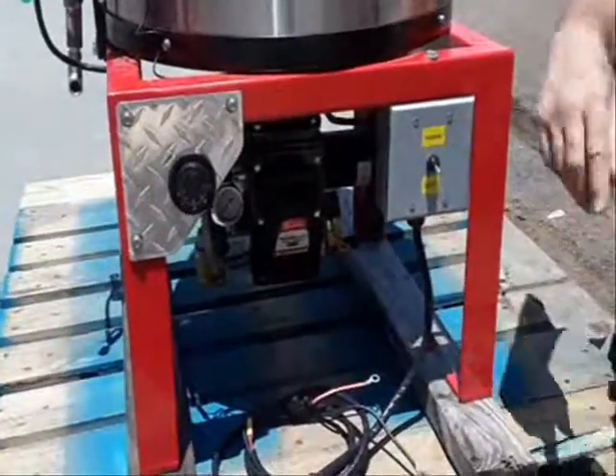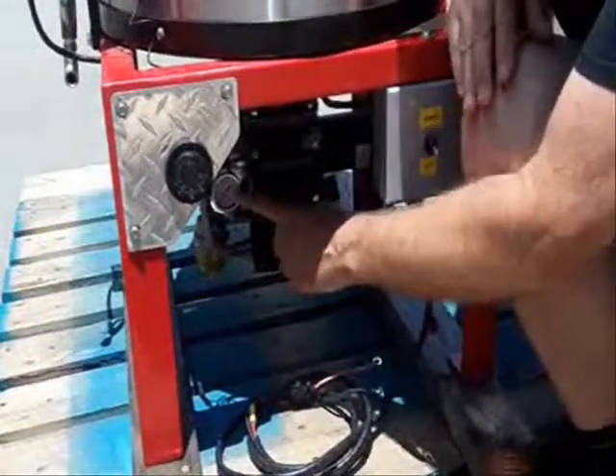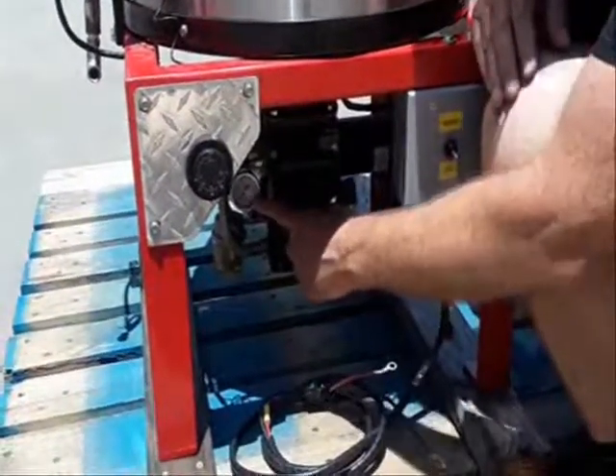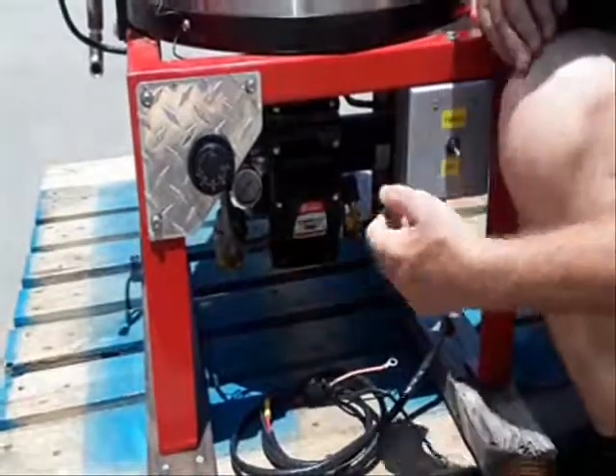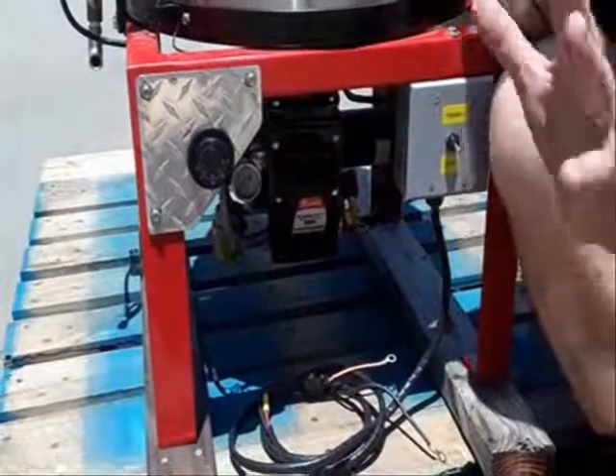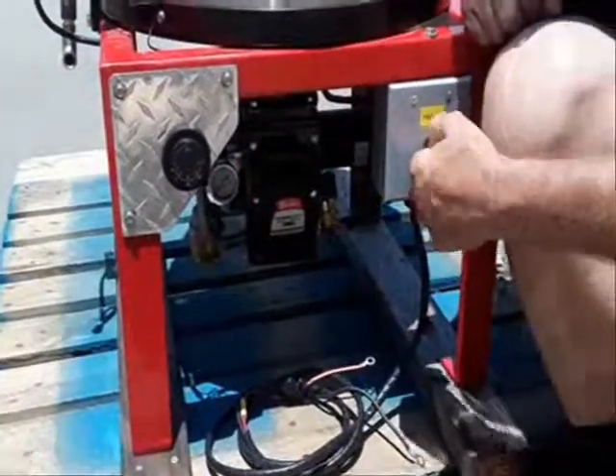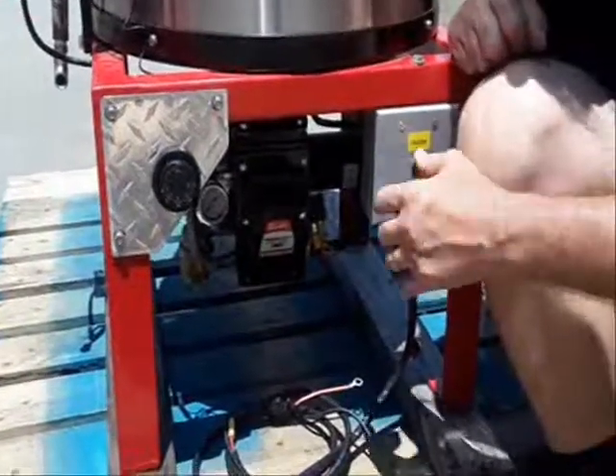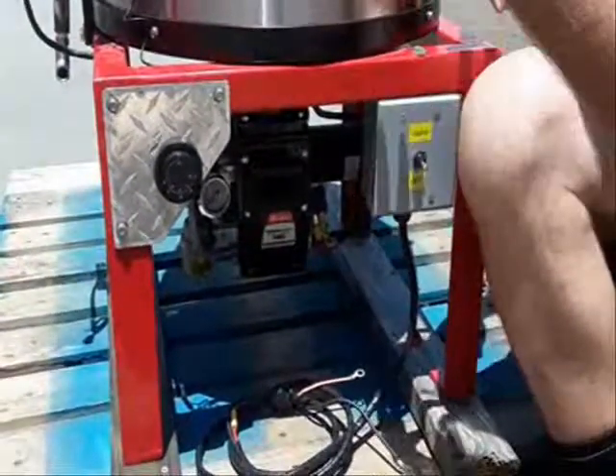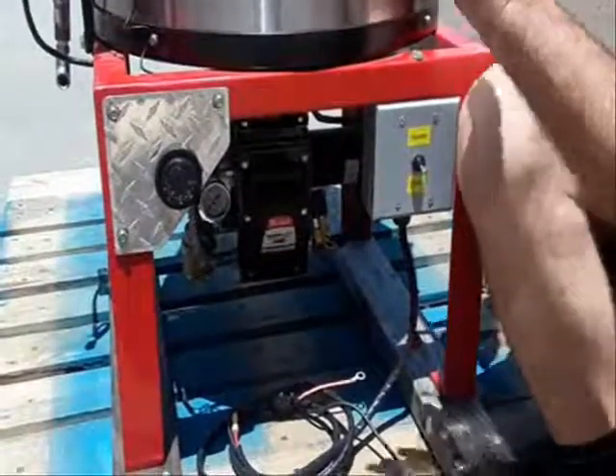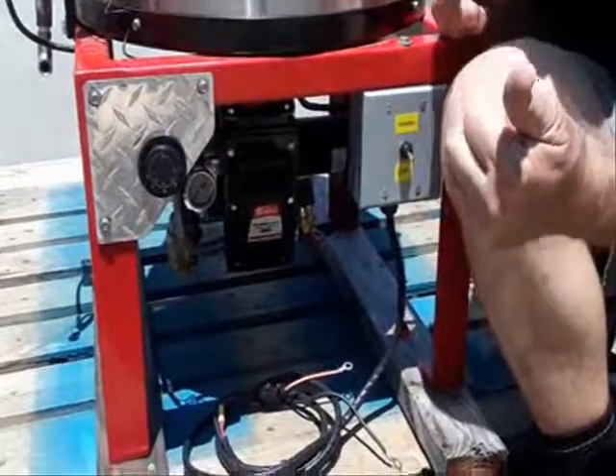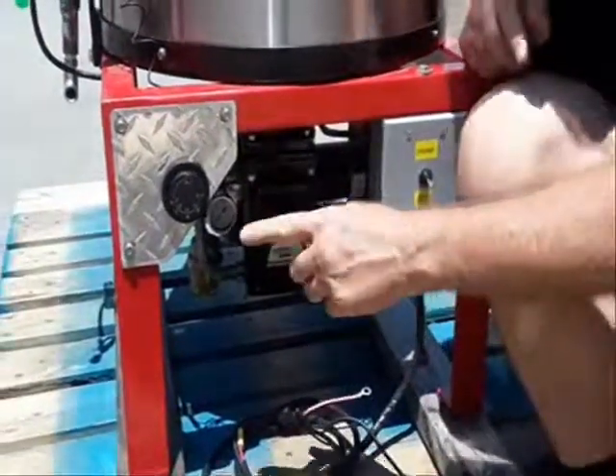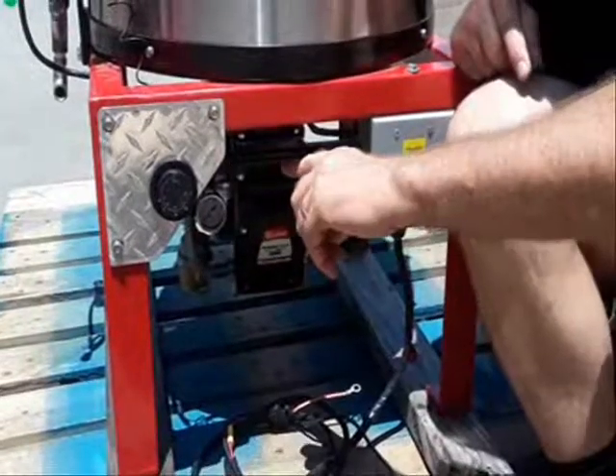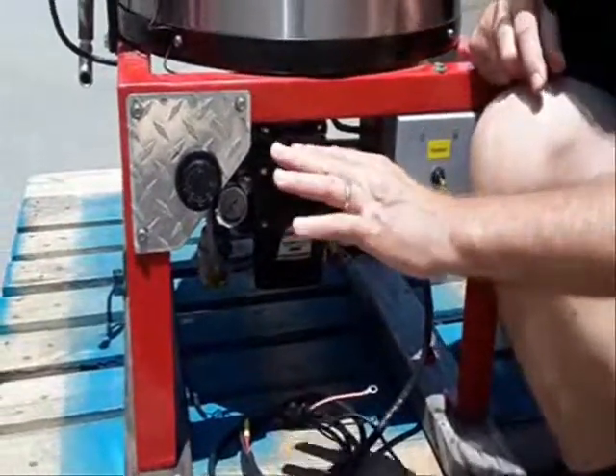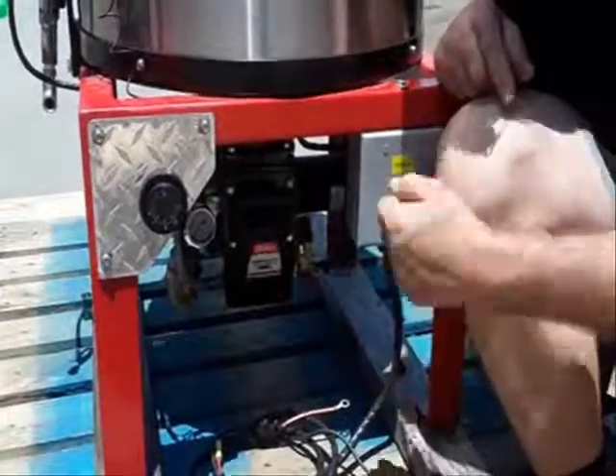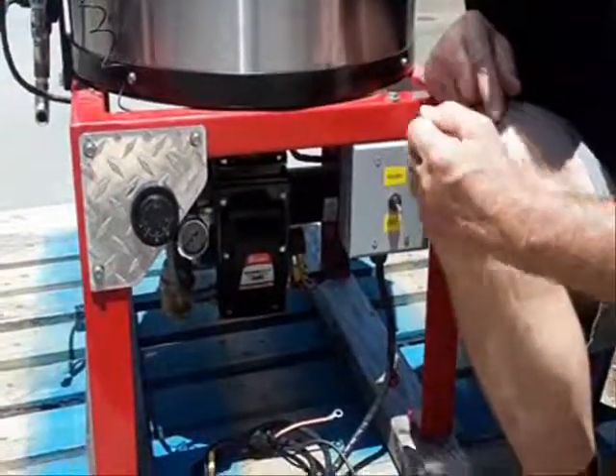Okay, now you've got a fuel pressure gauge on here that indicates the fuel pressure. When you flip on the heater, whenever you're going to run the system, you're going to turn the heater on and observe that it sounds like the air is blowing. You don't have fire yet because you didn't open the gun. The fuel pressure is going to read between 100 and 120 psi. That's pretty standard. It'll always be the same pressure every time you flip on the switch. If it ever acts differently, you've got a problem.